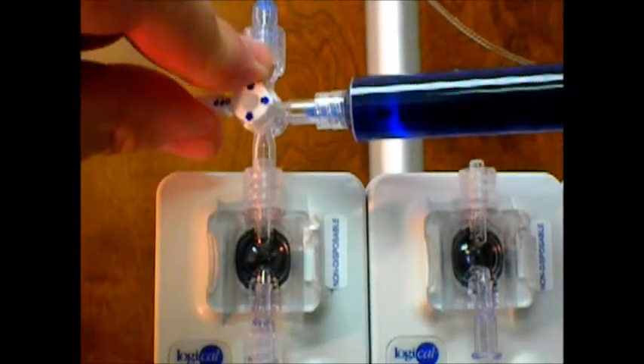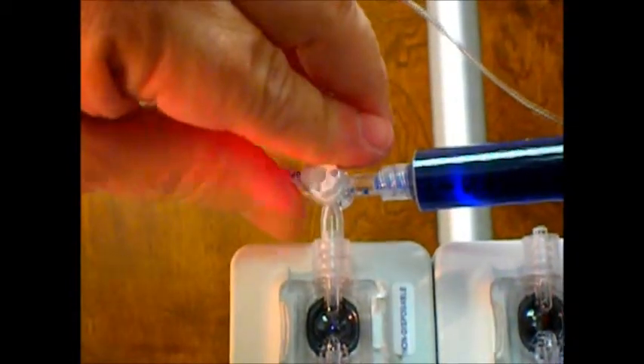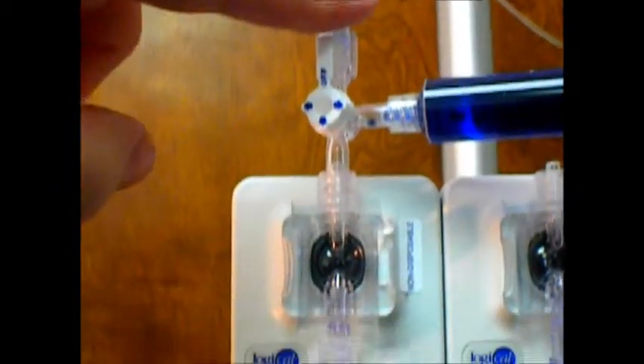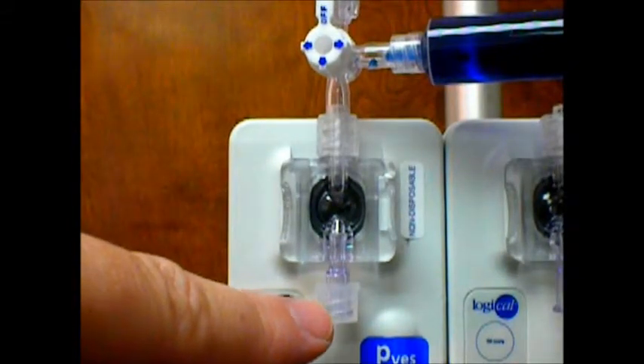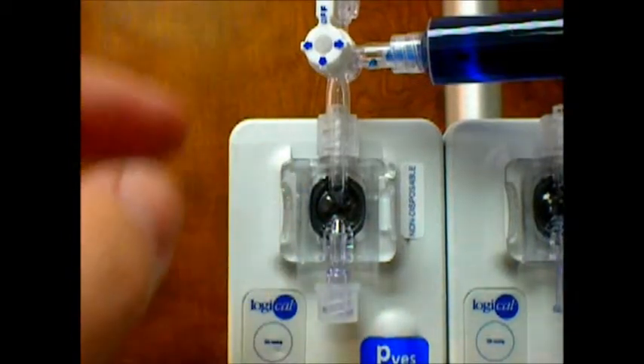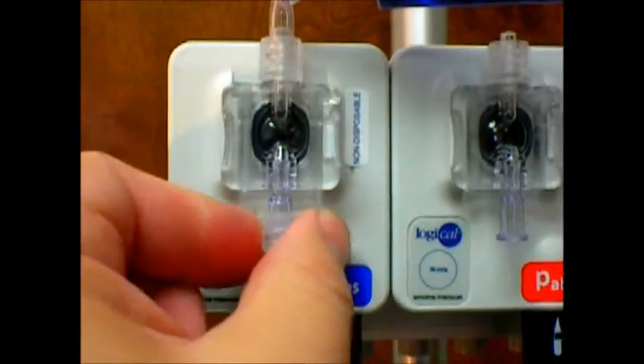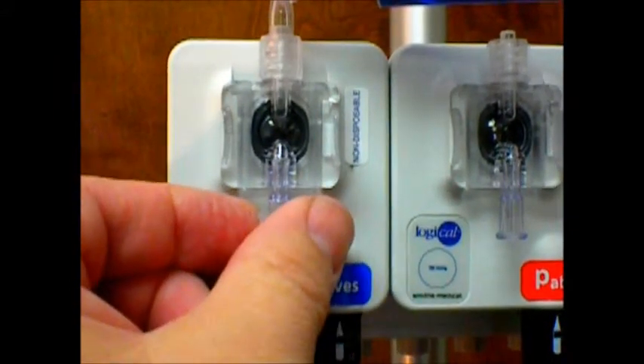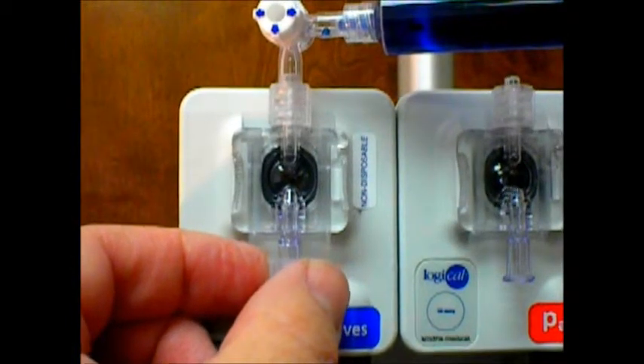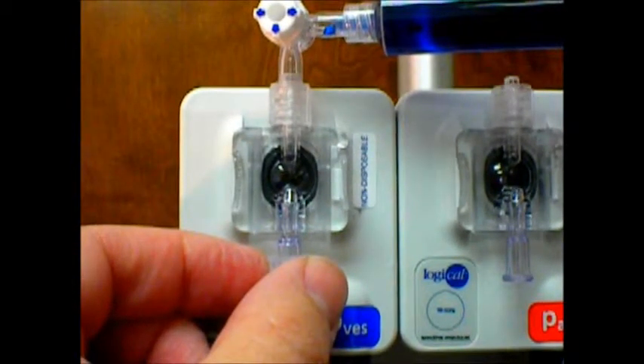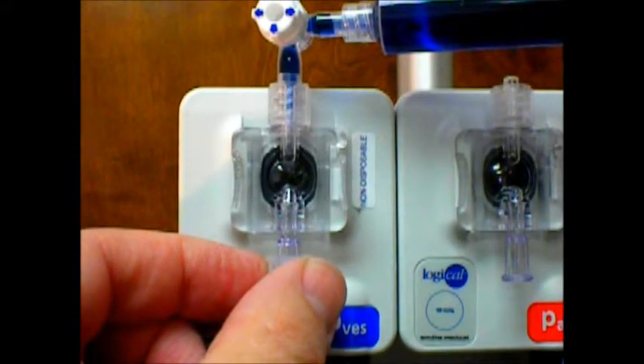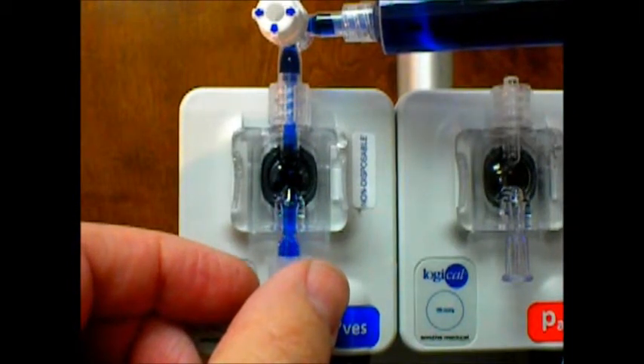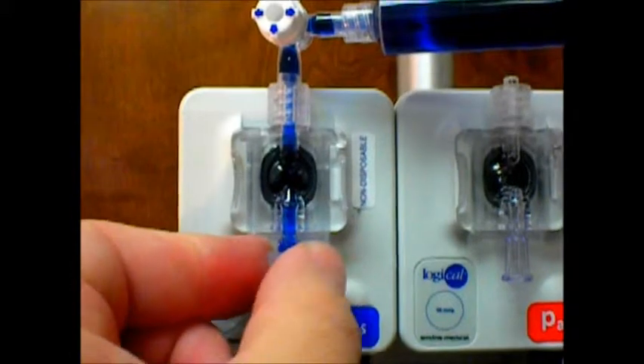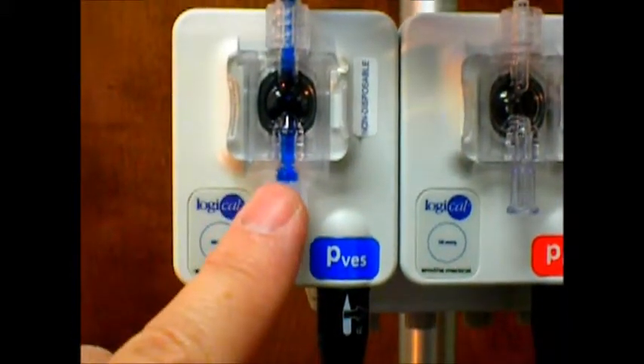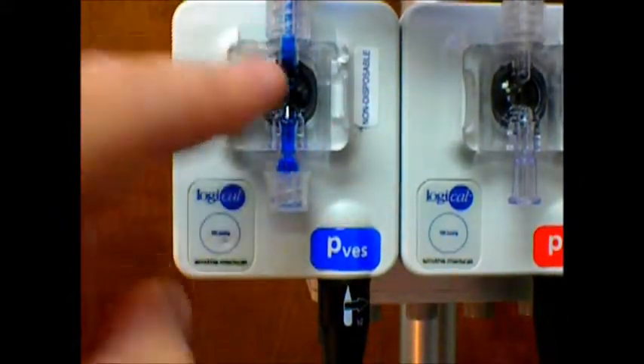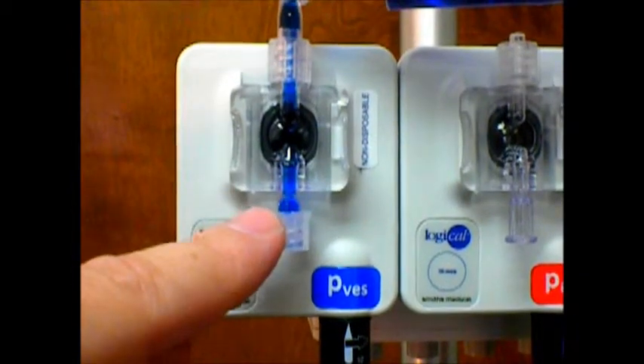I'm going to take the stopcock and close it off to the tubing that goes to the patient, because what we're going to do is we're going to flush the water through the pressure cartridge to get all the air out of that. I'm going to take off the cap on the bottom, and actually if you just loosen it so you don't lose it, but you can take it off all the way if you want. Then just very slowly, very gently flush the fluid through the transducer till it comes out the other end, and then you seal off that cap at the bottom. Tighten this back up. We're not going to be taking this off again, but we now have fluid all the way through here, and these transducers are so nice, you just don't get air bubbles in them.